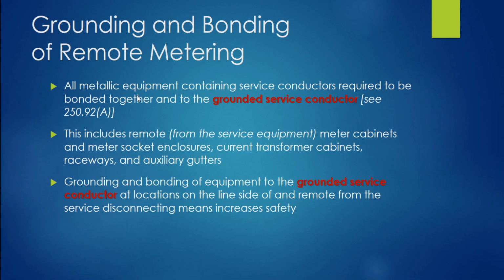All metallic equipment containing service conductors are required to be bonded together and to the grounded service conductor as stated in 250.92(A). So, we're going to keep it really simple. When you're dealing with the remote equipment, like a CT cabinet or a meter enclosure that is remote of, let's say, the structure, or it's downstream, maybe on the same structure, but it's further down the wall or it's remote from it, keep something in mind. It still has service conductors in it. So don't get lost in all the names, like if it was a meter disconnect or anything like that involved or interposed in the system. This is a remote meter location. It's still got service conductors in it.